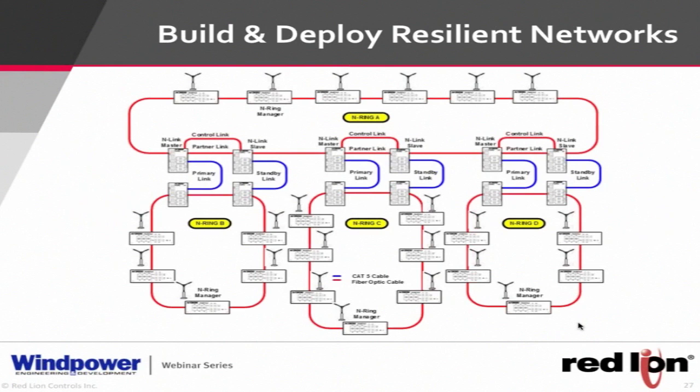And so we have redundant inputs on the power supply on all of our Ethernet switches, so you could have multiple power supplies, or you can have a power supply and a battery backup, however you felt most comfortable doing it. But let's say you were to have a power outage right here, say the switch at the very top. If you were to have that switch fail for a power outage or whatever it may be, the rest of the network is still up and going.